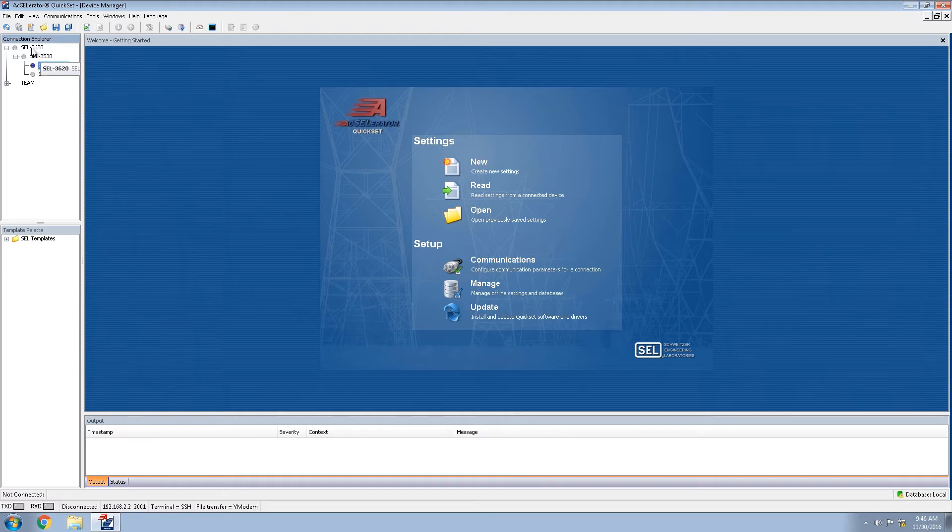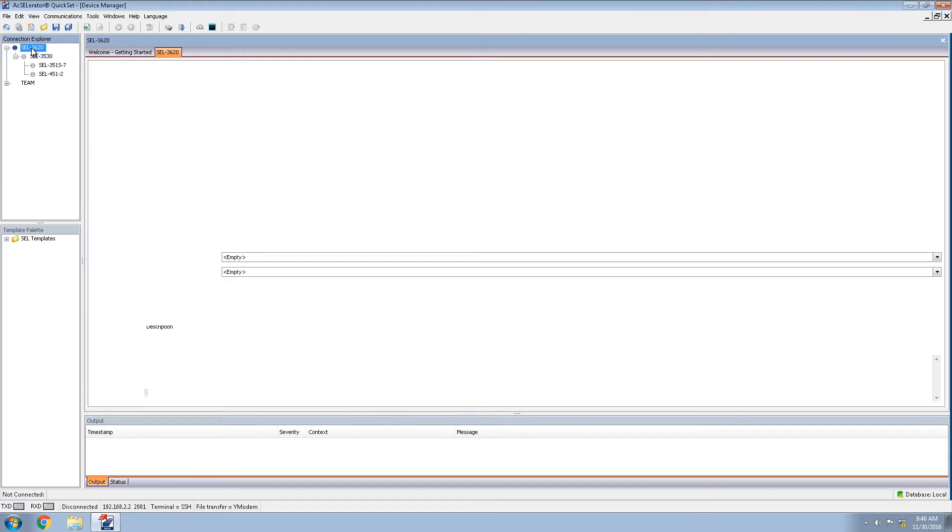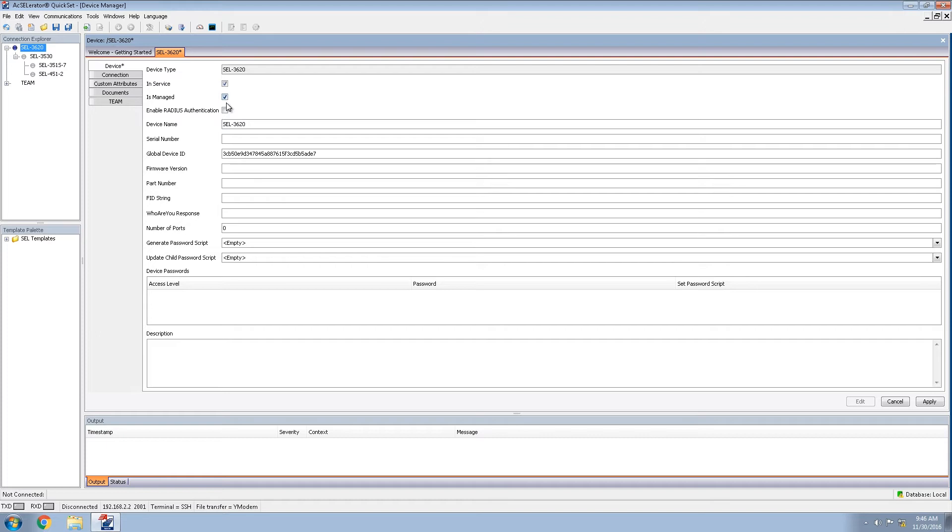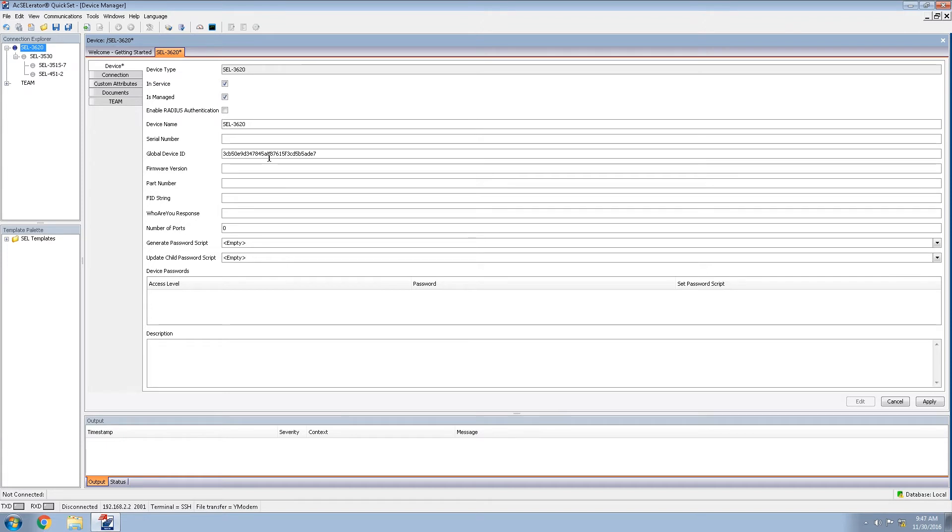In order to start configuring each of the devices we will double click on the device name. We'll click the edit button and we will want to make sure that this device is registered in service and is managed. If you're using RADIUS for your central authentication, you will also select the enable RADIUS authentication. The global device ID setting is very important to the system. You'll see that it comes with a default long string. It is required that it is unique for your entire system. However, it is more beneficial to have it be something meaningful to you. In this case, we will be labeling this SEL 3620.